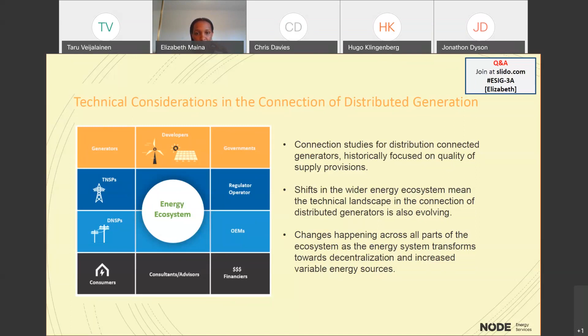One of the big considerations from a voltage perspective when connecting distributed projects to the network is the generator's voltage control strategy. Historically this was all about voltage step considerations. There are different distribution codes as projects connect at LV to medium voltage level—for example in Victoria, you must manage your step change to within 3% at the 66kV level or 5% at the 22kV level.